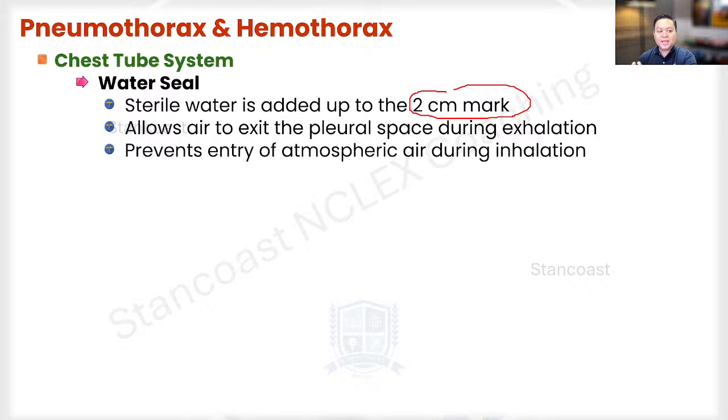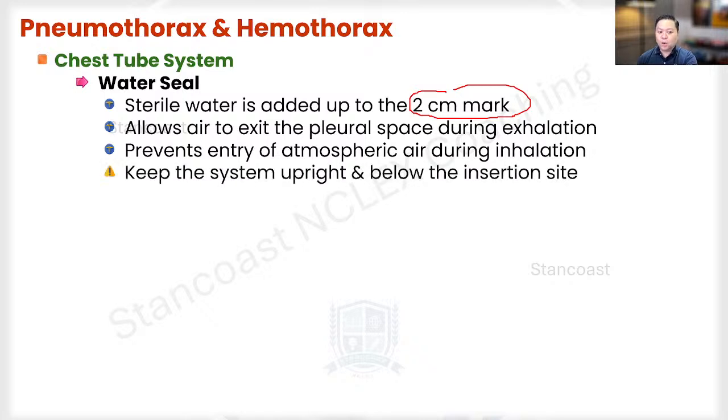Now, what are we going to do here? It definitely needs to be the position of the chamber. I mean, the entire container itself should be placed in an upright position. We don't want it tilting. Make sure that it is placed on a flat surface. Make sure that it is well supported so it doesn't drop or tilt to one side. Okay? We want to make sure that the water seal is kept at 2 centimeters.